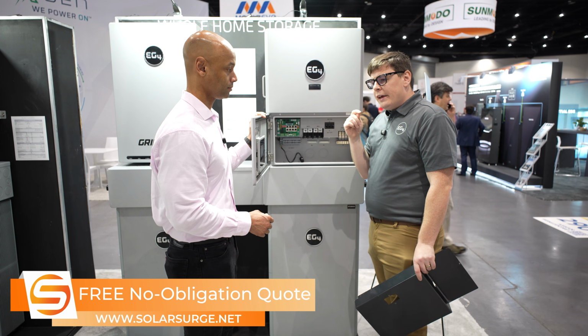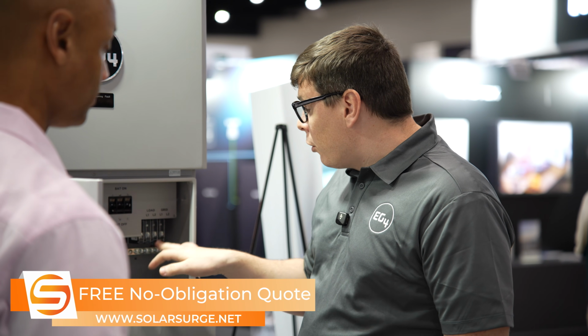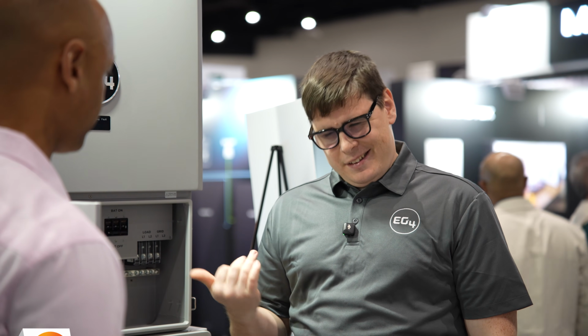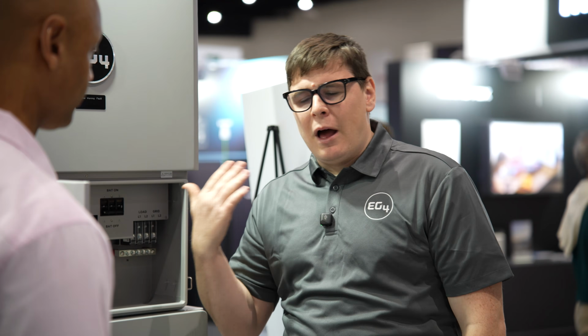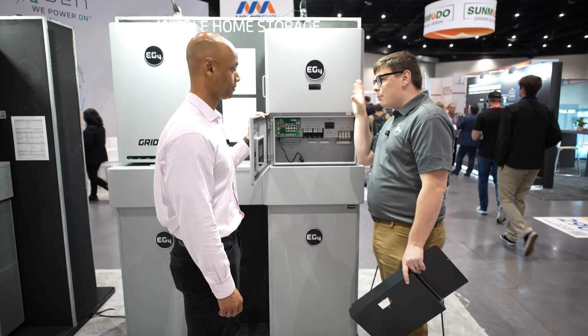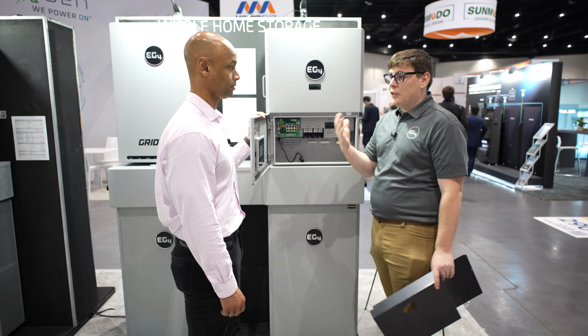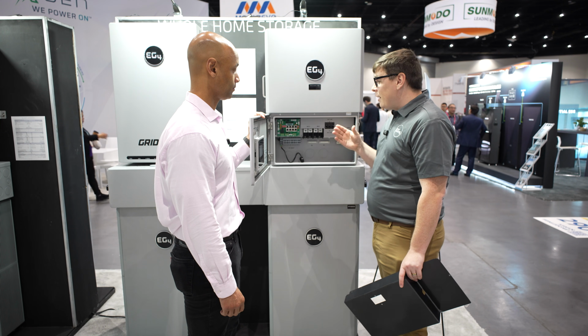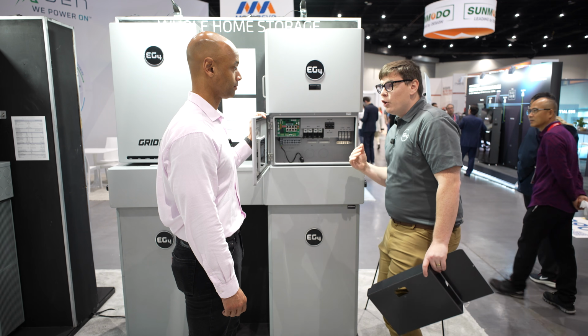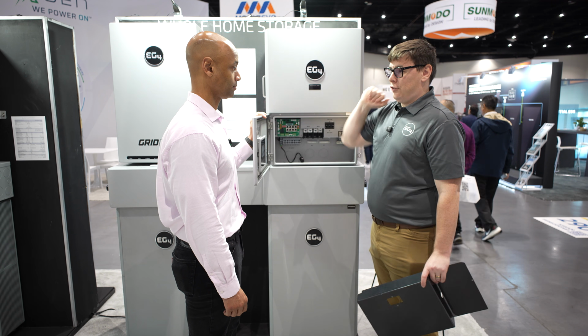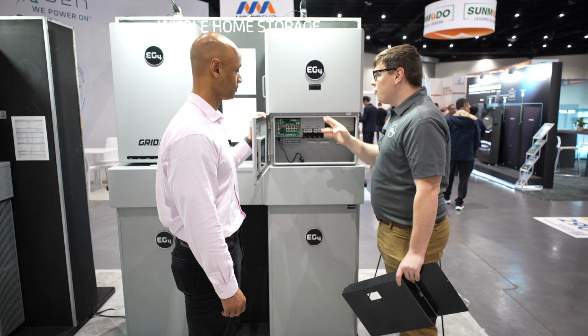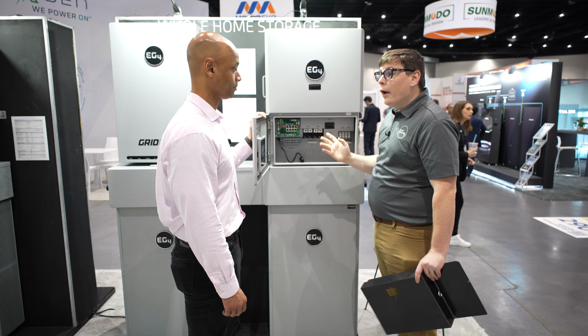We said, look, if you're using it off-grid, the generator will go into the grid side, which is the AC input. And we can actually boost and clean up the generator a lot more with the grid input of this inverter. Most hybrid inverters, the generator input doesn't fix the generator as much. So we said, if you're using the grid, you're going to use the GridBoss, and you could just tie into the GridBoss's generator input.